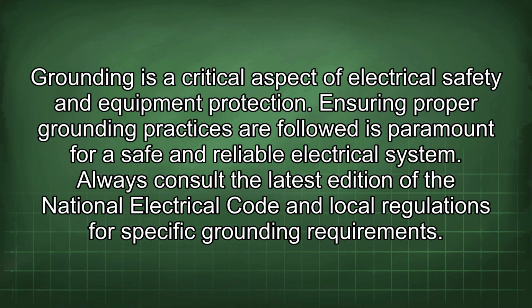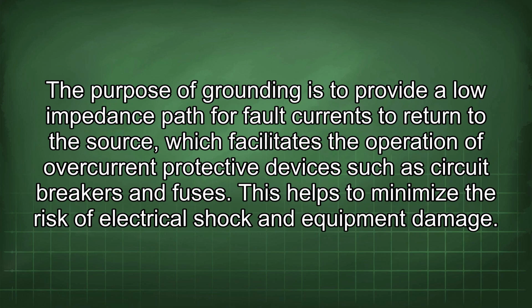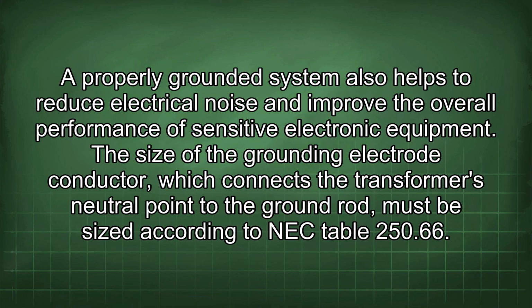Grounding is a critical aspect of electrical safety and equipment protection. Ensuring proper grounding practices are followed is paramount for a safe and reliable electrical system. Always consult the latest edition of the National Electrical Code and local regulations for specific grounding requirements. The purpose of grounding is to provide a low impedance path for fault currents to return to the source, which facilitates the operation of overcurrent protective devices such as circuit breakers and fuses. This helps to minimize the risk of electrical shock and equipment damage. A properly grounded system also helps to reduce electrical noise and improve the overall performance of sensitive electronic equipment.